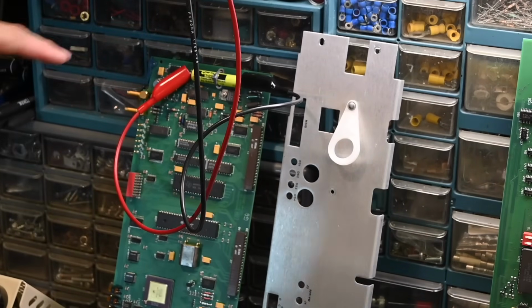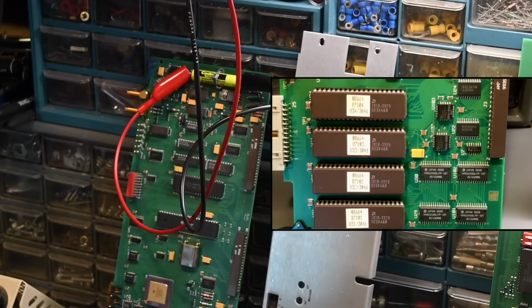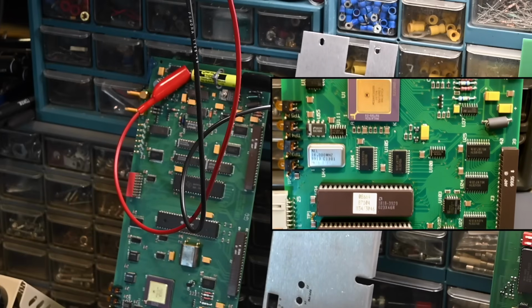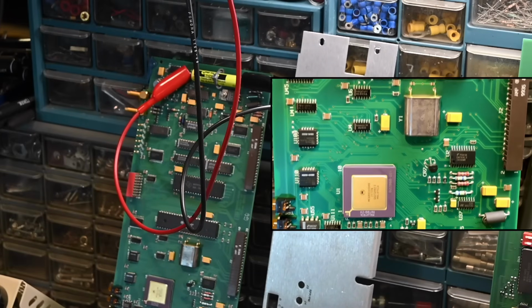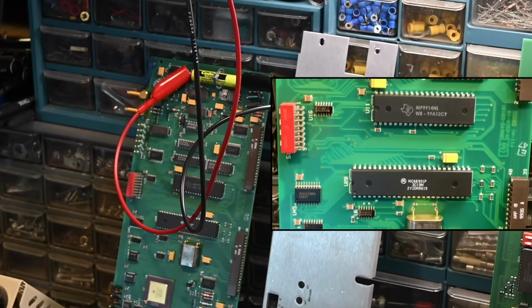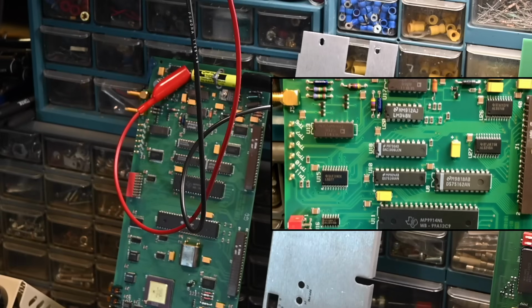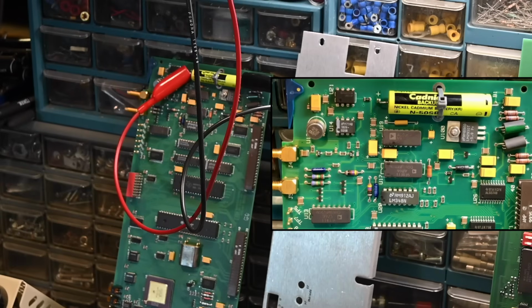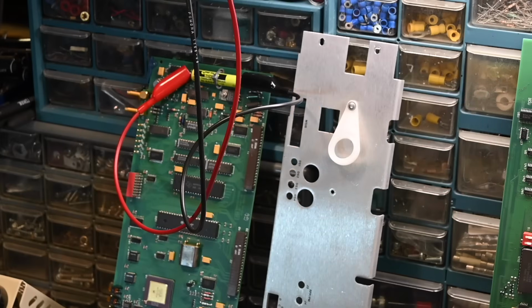This is the NiCad battery right here, this little yellow battery. So it's just a 45 milliamp hour rating, so it's a very small NiCad. So right now I'm charging it up just to make sure that it has a full charge, and then I'm going to do a discharge test on the NiCad and see if it holds up. If it performs and meets its rated specs, then I'm going to leave it alone. There's no corrosion, it looks to be in good condition, so it looks to be a good quality battery. Probably original, but I'm inclined to leave it alone if it's still working okay. And again, if it holds up with the full rated capacity, then that means it's in good condition. But if it doesn't work and discharges very quickly and doesn't have the capacity that it should, then I'll definitely have to replace it.